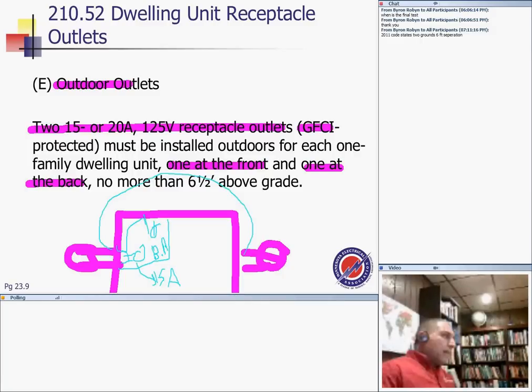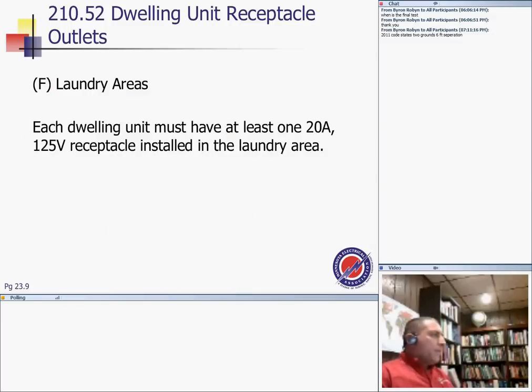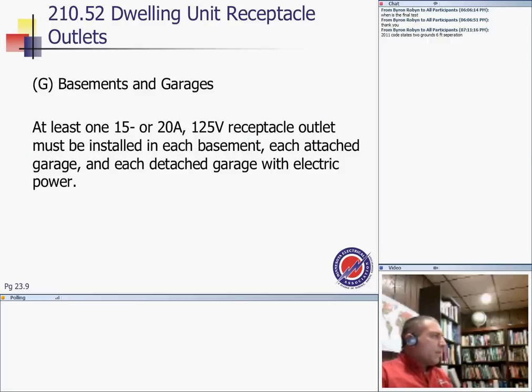Nothing wrong with that, guys. There's nothing wrong with it. The only restriction is if these receptacles inside were in the kitchen or the bathroom. Then don't do it. With that one, keep in mind that your receptacle has to maintain 6 feet 6 inches. Laundry. The laundry, my friend, you have to have one receptacle, 20 amp, for the laundry. One 20 amp circuit, one receptacle for laundry.